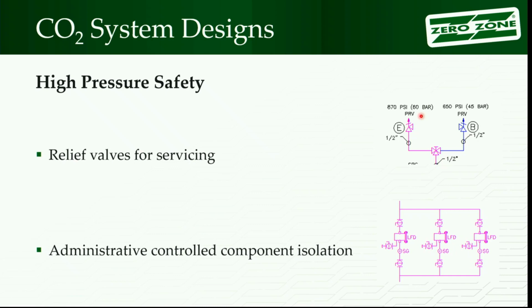So administrative controls have the advantage, they don't have all those little check valves flopping around in them. They don't have a safety relief valve. Without the check valve and without the safety relief valve, when it comes to servicing, it's a little easier, more what I'm used to with that. So you tend to see that more in industrial applications, they will look for that. They have more confidence, they have the same group running it, it's in their own facility, their own maintenance crew on it. You will not see administrative controls used with automatic valves. If you have an automatic valve, you will have one of those other automated safeties on there.